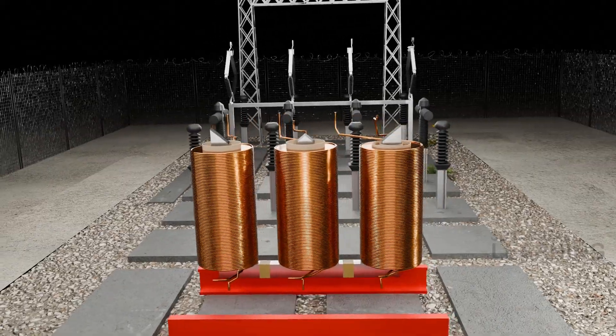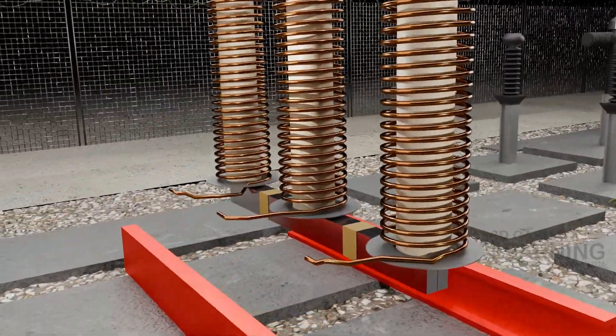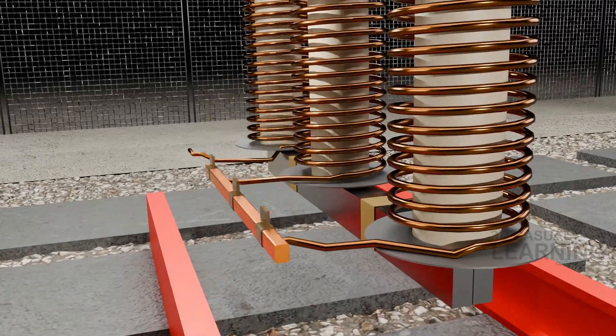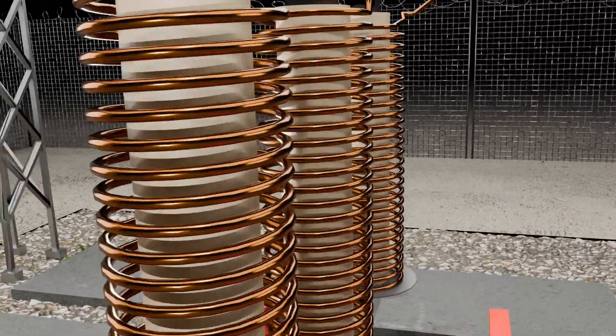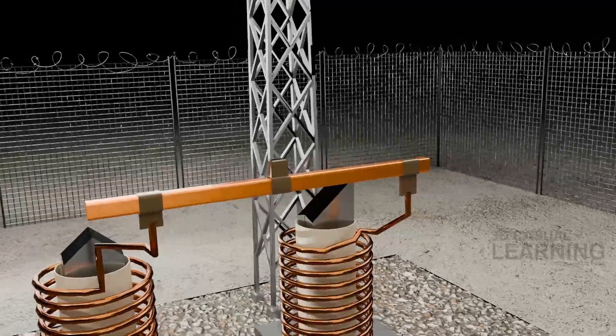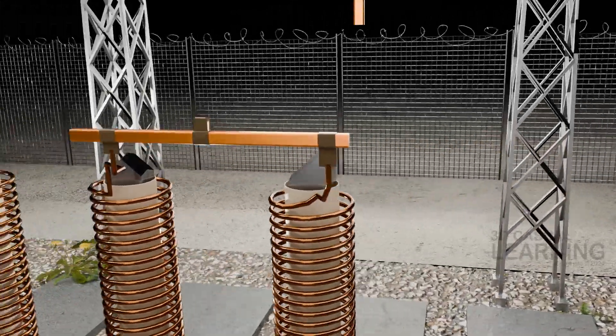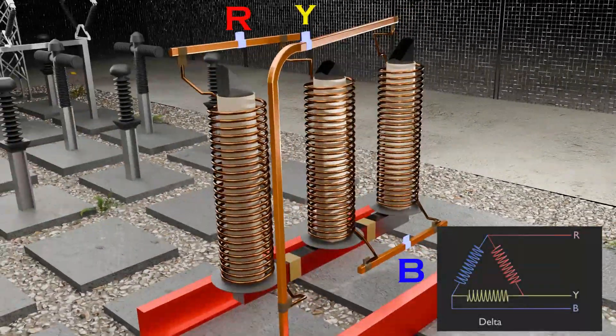In a delta connection, the primary coils are connected in a closed loop in the shape of a triangle. Each winding is connected between two phases of the three-phase electrical system, forming a closed circuit. The delta connection is commonly used on the high-voltage side of the transformer in power distribution systems.